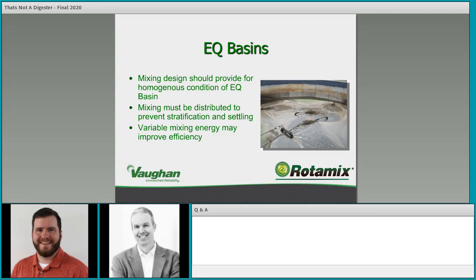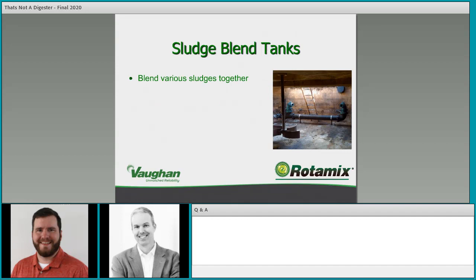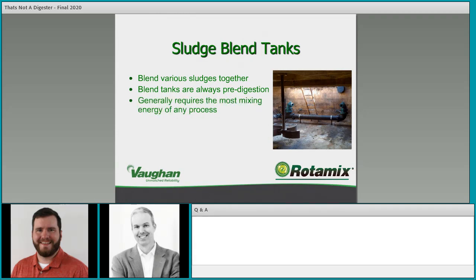Sludge blend tanks are defined by blending various sludges together. Blend tanks receive multiple sludges and blend them into one cohesive, homogenized sludge ready for the next process. They're almost always pre-digestion. They generally require the most mixing energy of any process because they're seeing the highest concentration sludges in your facility — thickened sludges, waste activated sludge, primary sludge, and any additional received sludges all being blended together.